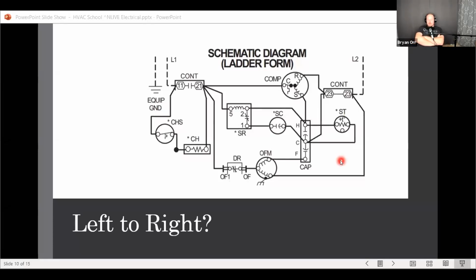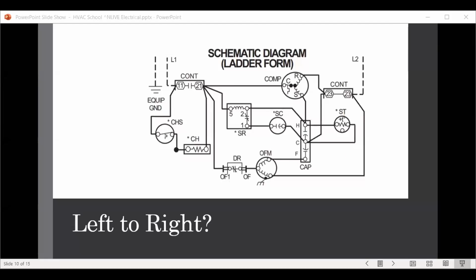And measuring to ground in general is just not the best practice. But just out of curiosity, what are some times that measuring to ground is a good practice? Measuring to ground for me is a safety piece to just find out if there is voltage present before I go sticking my fingers in there, because I'm going to create, or the technician, whoever is going to go in there, is going to create that path to ground. So anything I'm going to touch, I want to know if there's power on it. Absolutely. And that's a really good point.